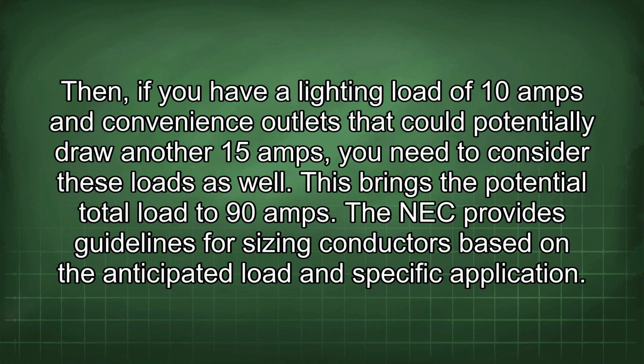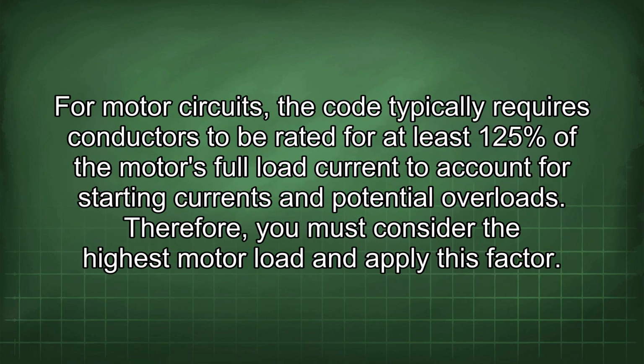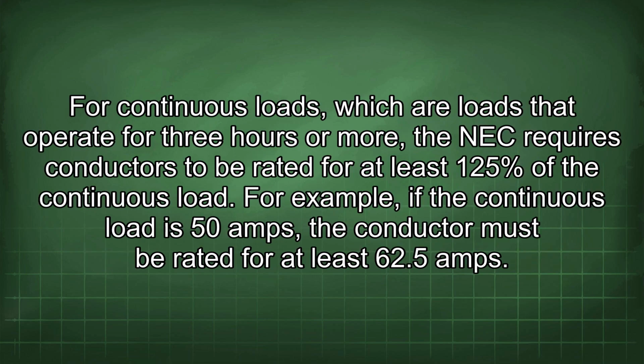The NEC provides guidelines for sizing conductors based on the anticipated load and specific application. For motor circuits, the code typically requires conductors to be rated for at least 125% of the motor's full load current to account for starting currents and potential overloads. Therefore, you must consider the highest motor load and apply this factor. For continuous loads, which are loads that operate for 3 hours or more, the NEC requires conductors to be rated for at least 125% of the continuous load. For example, if the continuous load is 50 amps, the conductor must be rated for at least 62.5 amps.